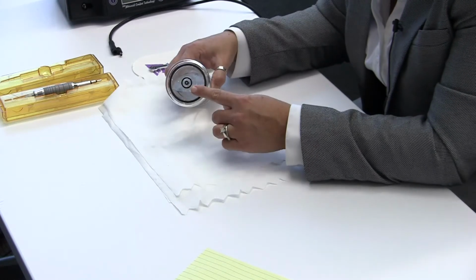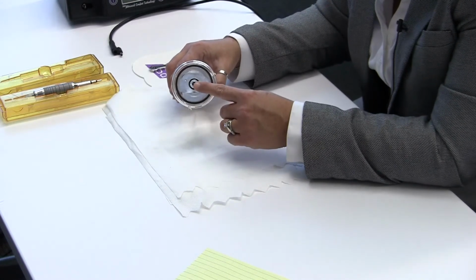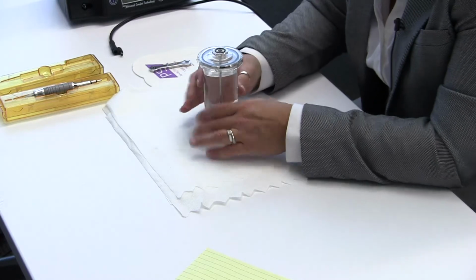One of the ways that we can do that is by unscrewing the bottle itself and put just water on here and then run through each bottle. This will happen sometimes at this tip here. Medication can get clogged in the tip of the bottle. And we want to make certain that that's been cleaned out and that that's not what the issue is. So we would make sure that we would try different bottles that came with your unit, and also clean this port underneath here. There's a little hole that you can then tip the unit and be able to clean out that hole to make sure nothing is lodged or stuck there. That will also help us to determine if it's something that's with the unit or with the bottle itself.